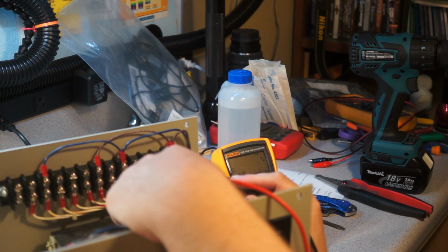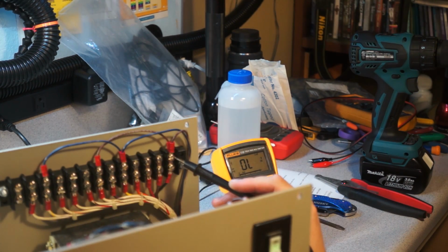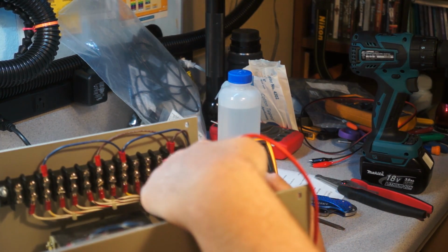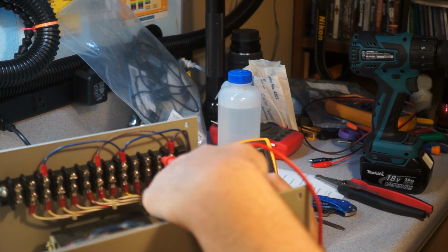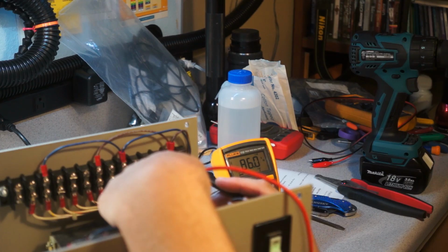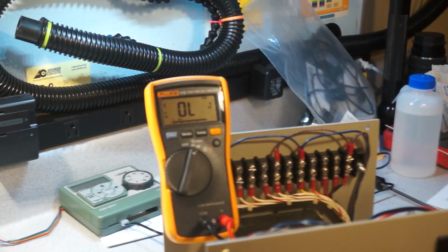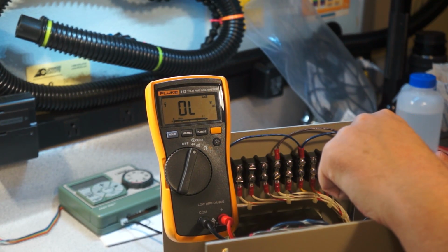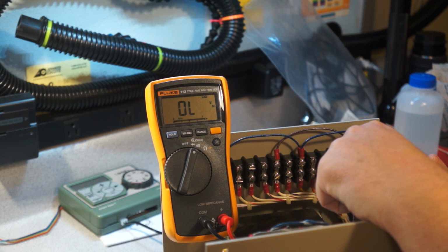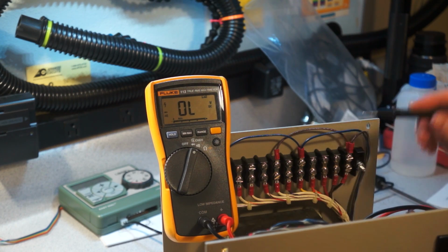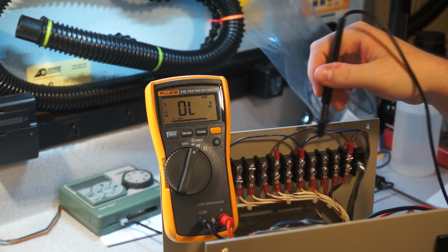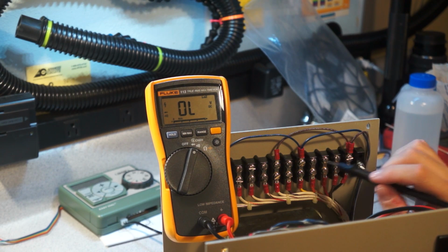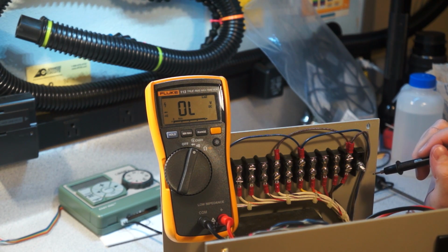Look at that — I bet this is to let them use this in Japan, or in areas with low line voltage. So if your line voltage is around 85, you use these two taps and still get about 86. Here's 96, 105 — you could use these taps with your primary to give you 120 volts output. So it looks like you could probably use this for line stabilization if you wanted to.